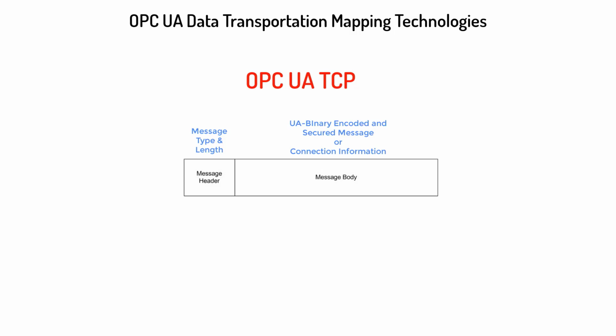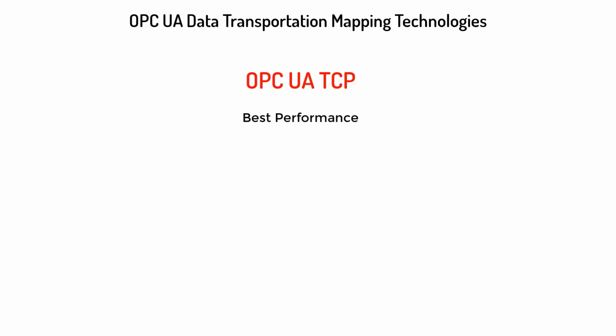If it contains a UA binary encoded message, that message ends up being forwarded to the secure channel layer, where it is decrypted and pushed up the stack, where it is decoded and presented as information to the application layer. In conclusion, UA TCP protocol offers the best performance with the least amount of overhead, uses minimal resources, and is therefore preferred for devices at control field level in particular.